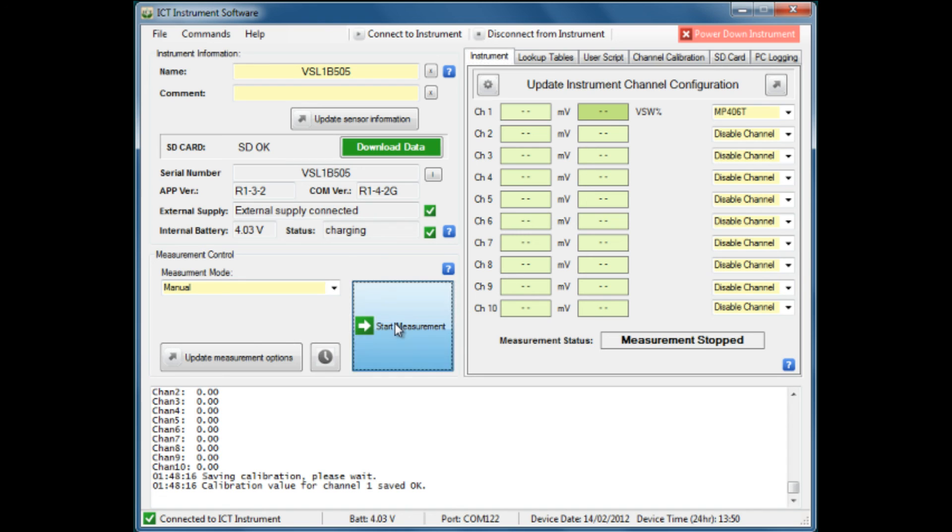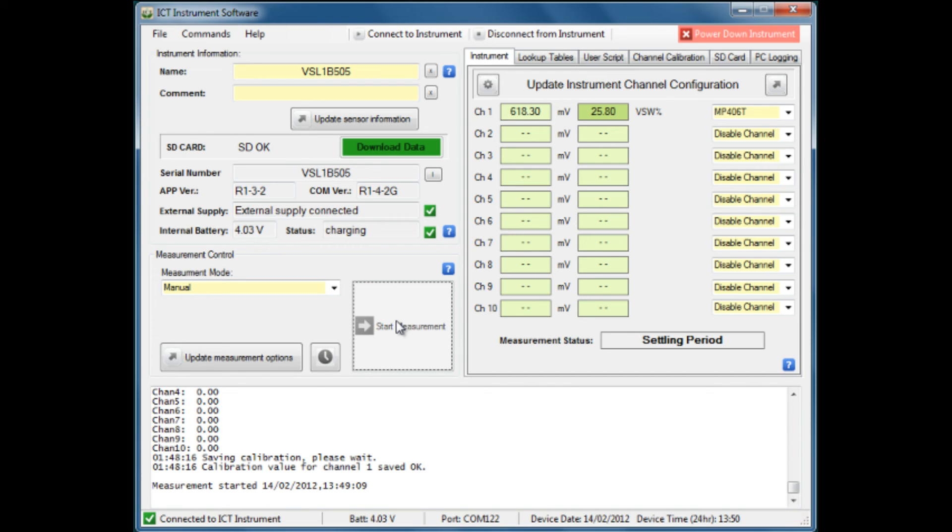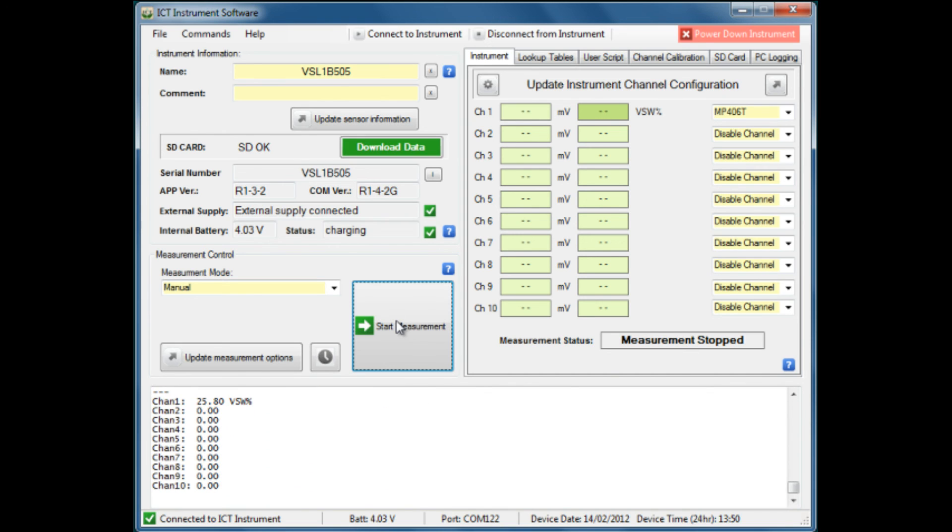The final step to confirm what's happening is that we actually take a measurement from the sensor and confirm that the results we get are what we expect to see. If we're happy with that, we can see down here in the dialog the new value that the sensor is measuring, and if that's correct, we are finished.